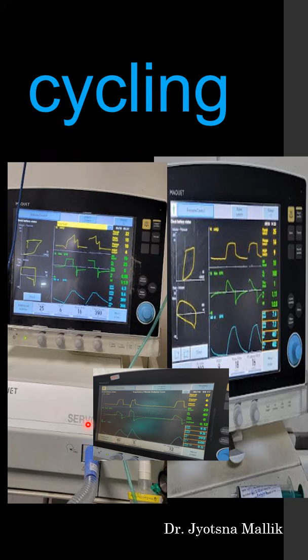In pressure control mode, time is the cycle. Once the TI is reached, the exhalation valve opens and exhalation starts. In the pressure support mode, once the percentage of peak flow is achieved, that is generally 25 to 30% by default, exhalation starts.